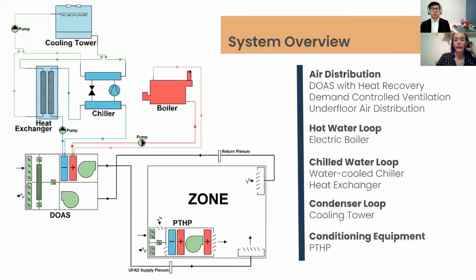The zones are conditioned by air source packaged terminal heat pumps that are designed for cold climate with a supplementary electric coil. The packaged terminal heat pumps showed to be 54% more efficient than fan coil units in terms of heating when compared in EnergyPlus.